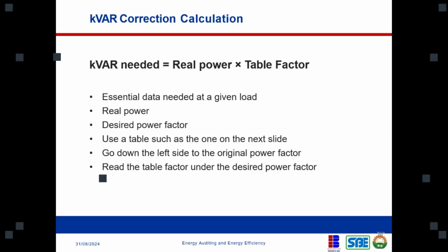It's a simple calculation. In most cases you will know what the real power is. There's a table factor that you multiply with the real power to know the size of the capacitor bank needed to correct a power factor. We're going to demonstrate that. Don't worry if you don't understand this from the formula. The essential data needed is the real power and the desired power factor. This is just an example illustration of how this can be calculated.